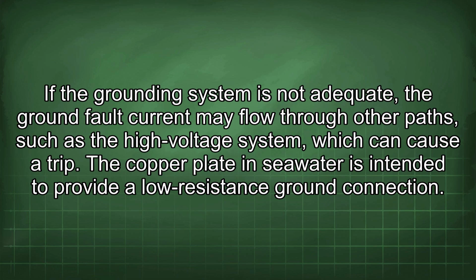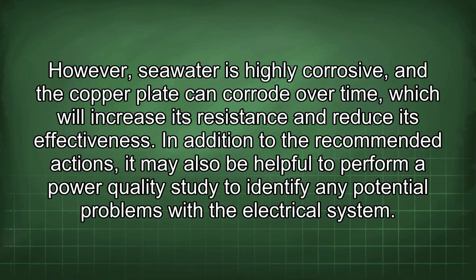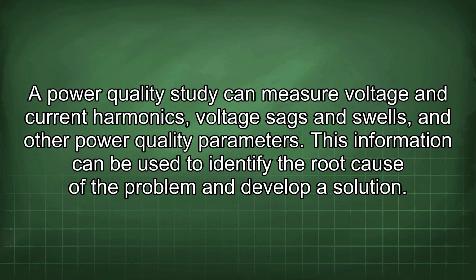The copper plate in seawater is intended to provide a low resistance ground connection. However, seawater is highly corrosive, and the copper plate can corrode over time, which will increase its resistance and reduce its effectiveness. In addition to the recommended actions, it may also be helpful to perform a power quality study to identify any potential problems with the electrical system. A power quality study can measure voltage and current harmonics, voltage sags and swells, and other power quality parameters. This information can be used to identify the root cause of the problem and develop a solution.